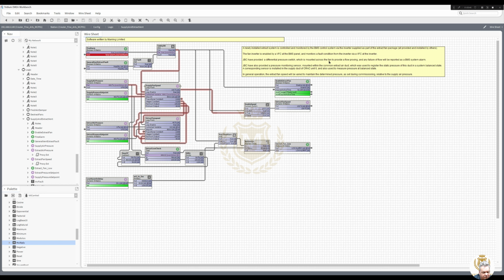Provide the flow proving. Oh, which is mounted across the fan to provide pressure switch and failure of the flow. Well, I can't see in my inputs, which has got to be an input, a flow switch. I've got that, digital input, extract vent, extract fault, and then I've got an output. Was it an output? I'm sure it was. Yeah, extract fan low. So I've got extract fan low, and I do have general vent extract fault, which is that one there. But I certainly do not have it in my IO.